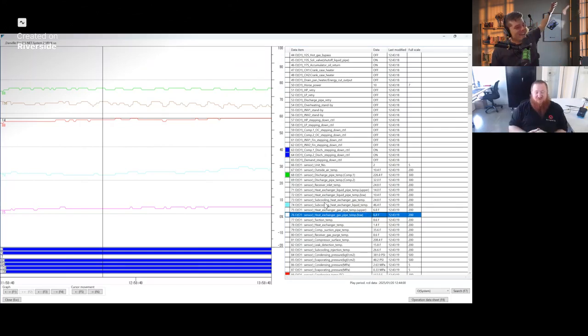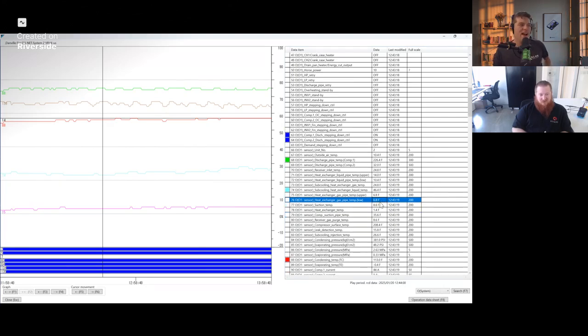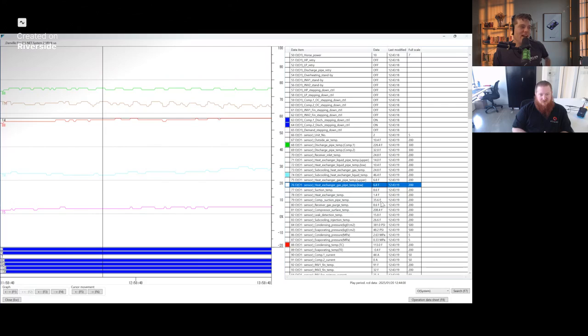So we've got liquid being generated at the indoor unit, and then it gets subcooled on the way to the outdoor unit. Then we go through the expansion valve, and then through the heat exchanger, and instead of picking up heat in the heat exchanger, we're getting colder and colder and colder. Then we're coming out the other side and going where? What's next? To our lovely accumulator.